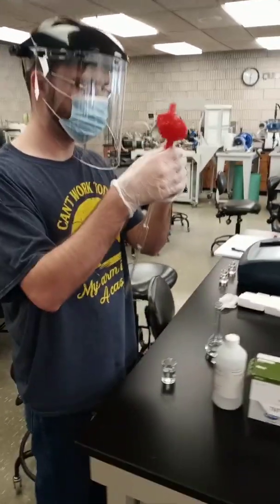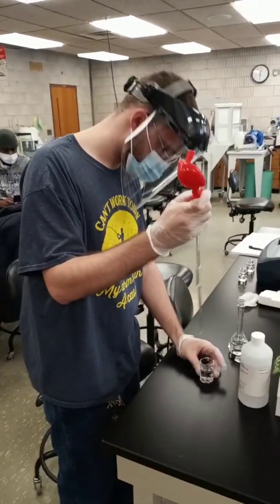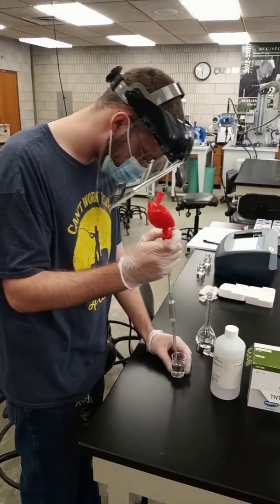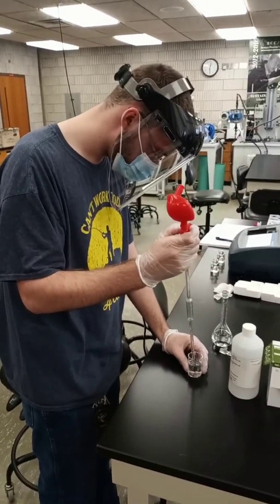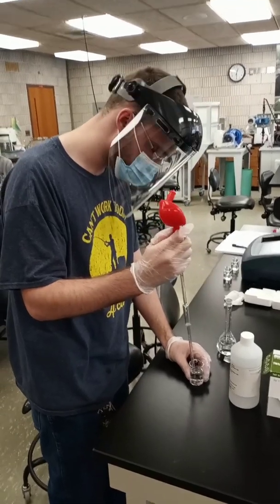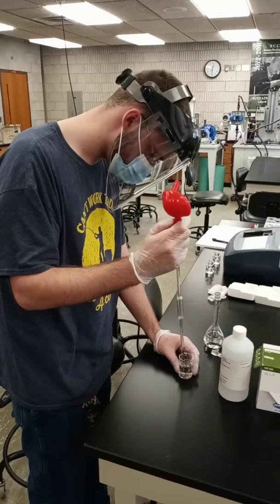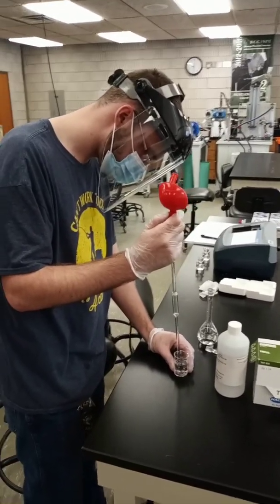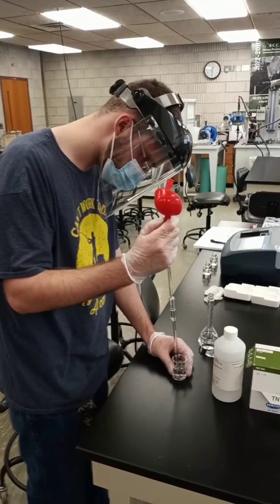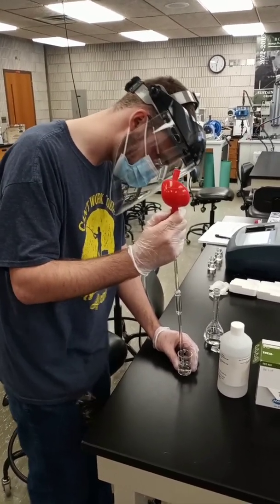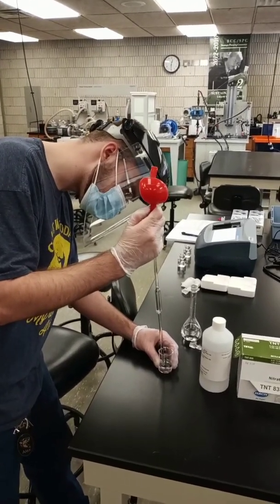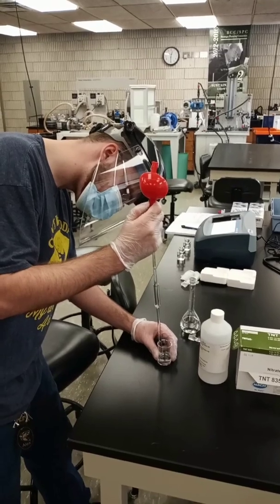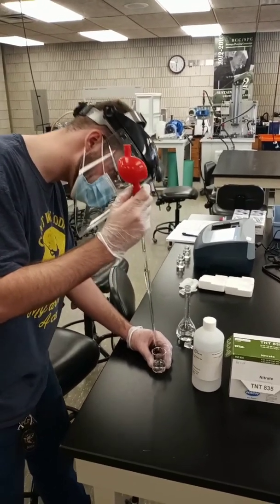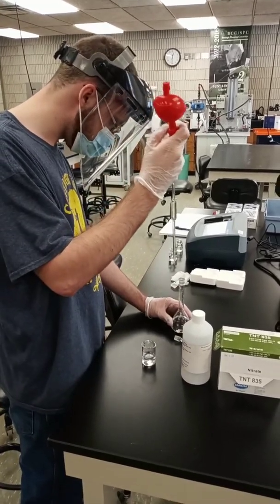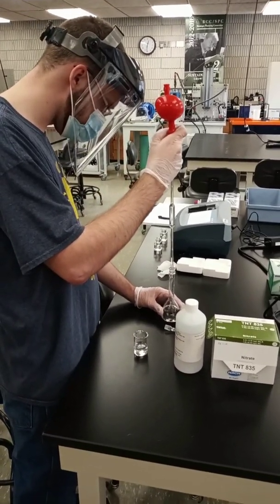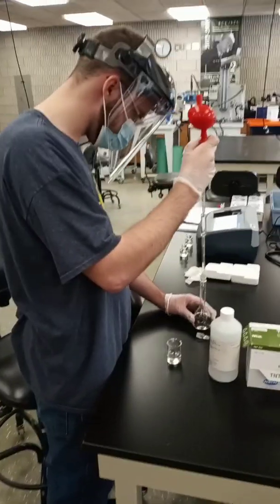Okay, here's Alex making a 10 part per million nitrate standard using a Class A volumetric pipette and a Class A volumetric flask. So he's going to transfer 10 mils of 100 milligram per liter sample into a 100 mil volumetric flask, so that we ultimately end up with a 10 milligram per liter sample or standard to run with our tests to check for accuracy.